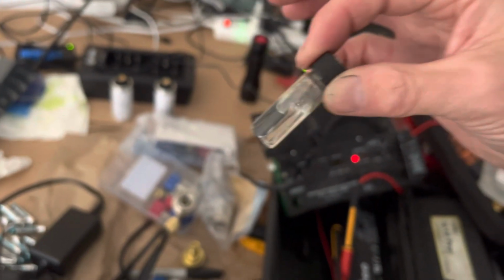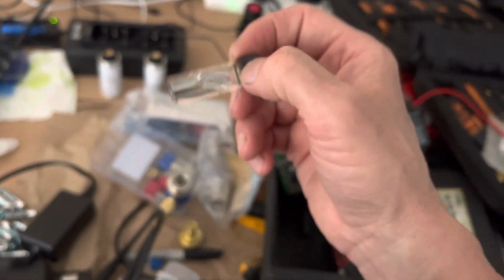A lot of guys have these and they've never ever recalibrated their sensors. They're going around looking for leaks with a leak detector that's no longer sensitive. And a lot of guys, they lose these or they no longer have the liquid in them. And because they cost a few dollars, I think they're 50 or 80 some dollars, they don't buy them again. But what good is a leak detector if you don't know it's working properly? And 99% of the guys out there have refrigerant leak detectors, and they have no way in hell to learn how to calibrate them or even test them.